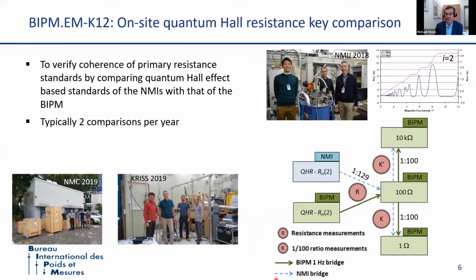The measurements are shown here on the right side. The green boxes represent material brought by the BIPM, and the blue boxes and arrows represent measurements made by the NMI. The first measurement is the value of a 100 ohm resistor calibrated against the second quantized Hall plateau of a Quantum Hall standard, done with both BIPM and NMI equipment. Then there are 2 resistance scalings, resistance ratios from 100 ohm up to 10 kilo ohm, down to 1 ohm, using a BIPM bridge and the NMI's bridge.